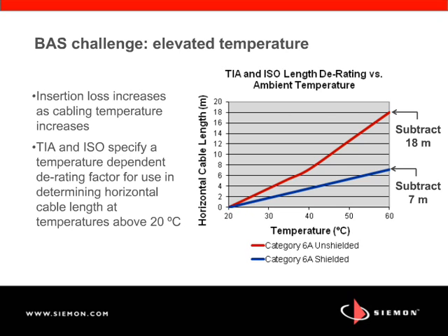One thing I do want to mention is what is the implication of this chart. The implication is for a 100-meter structured cabling length with a 6A UTP channel, that length of the overall channel has to be reduced to 82 meters to still meet the TIA insertion loss requirements at 60 degrees C. The overall length of a shielded 6A system only needs to be reduced to 93 meters to meet those requirements. So this does have implications for structured cabling deployment supporting remote powering applications over long lengths.